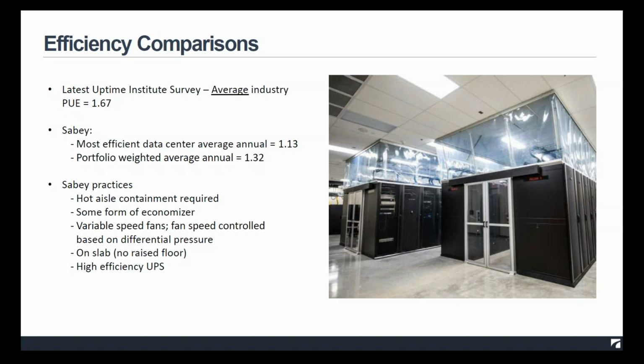So our most efficient data centers average an annual PUE of 1.13. Those are in our Central Washington facilities. And over our entire portfolio, our weighted average annual is 1.32. So you compare that to the industry average that the Uptime Institute found of 1.67, we're doing pretty good. And part of that, going back to the co-location industry, is you've seen a lot of new co-location data centers over, say, the last 10 to 15 years especially.